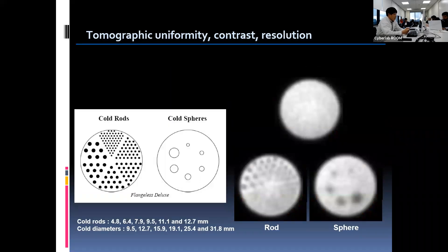Let's look at what the phantom consists of. The phantom contains three different segments. There are non-radioactive rods of different sizes in the bottom of the phantom for measuring spatial resolution. There are cold spheres of different sizes in the middle that are used for measuring contrast. And on the top of the phantom, there is a homogeneous radioactivity segment for evaluating uniformity. The images on the right show the reconstructed transaxial images for each segment.